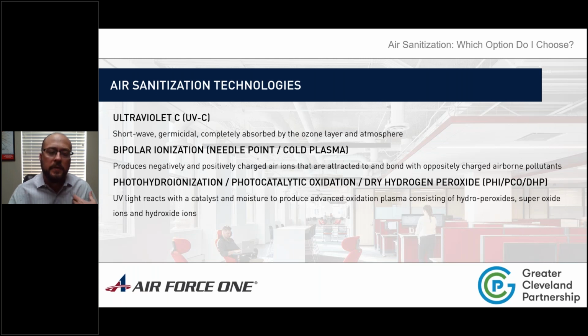The last grouping is what's commonly called photocatalytic oxidation, or PCO, and the more patented version using similar logic is photohydroionization, or PHI, sometimes called dry hydrogen peroxide, or DHP. This technology combines everything we've talked about so far. It uses UV light, not as the main disinfection source, but to react with a catalyst and moisture in the air, creating advanced hydroperoxides, superoxide ions, and hydroxide ions. In simple terms—and I think that's why it's been coined dry hydrogen peroxide—it goes through the chemical process of creating H2O2 without adding the chemical itself, through a naturally occurring phenomenon. That's the high-level overview; we'll dive more into that technology.